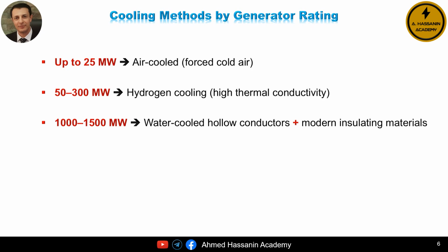We use forced air cooling, where cold air is pushed through the generator. At this power level, air is perfectly capable of carrying away the heat without any complications. As we move to larger generators, roughly in the range of 50 to 300 megawatts, air is no longer enough. Here, we switch to hydrogen cooling.